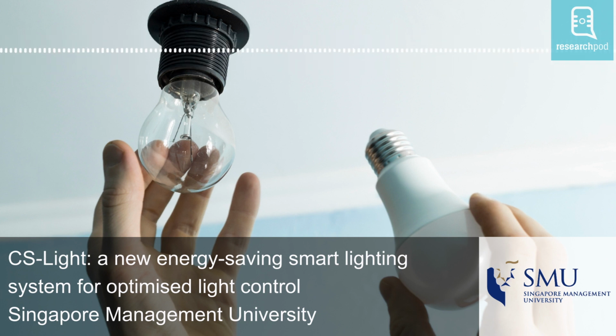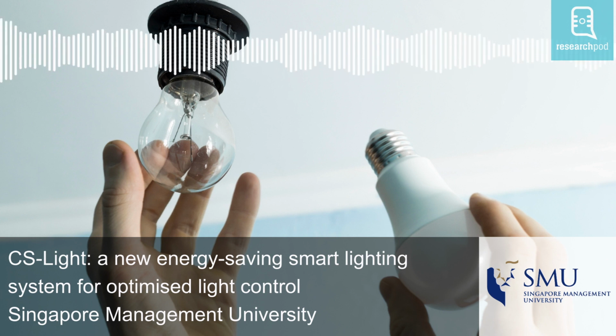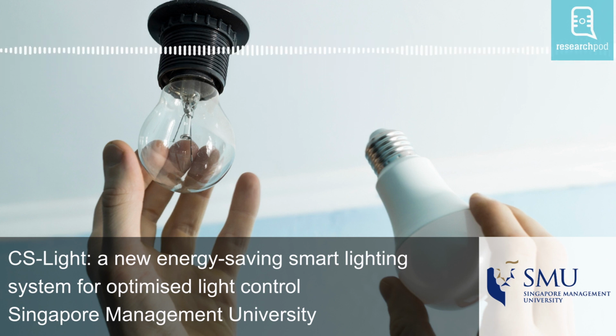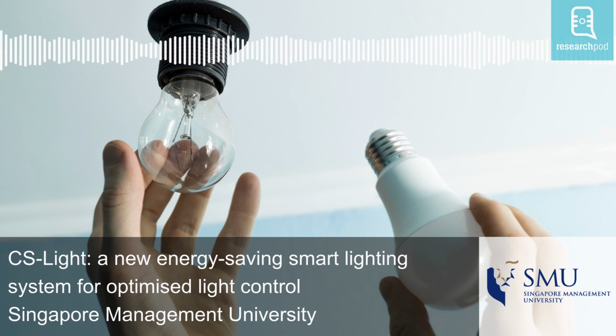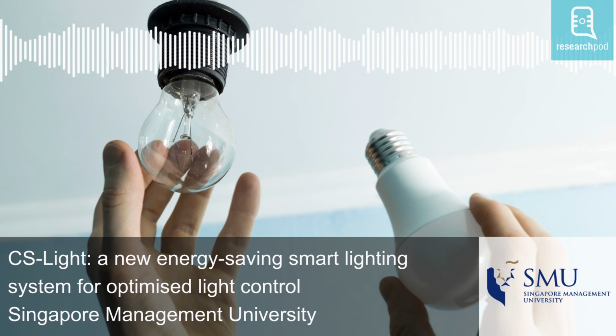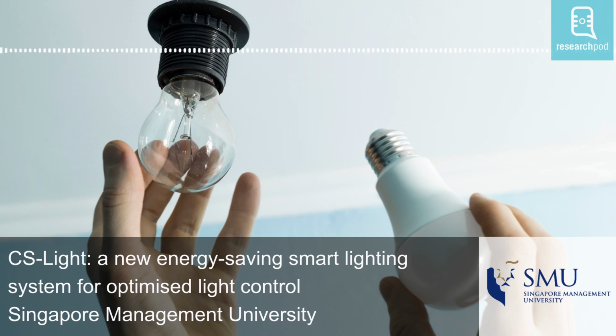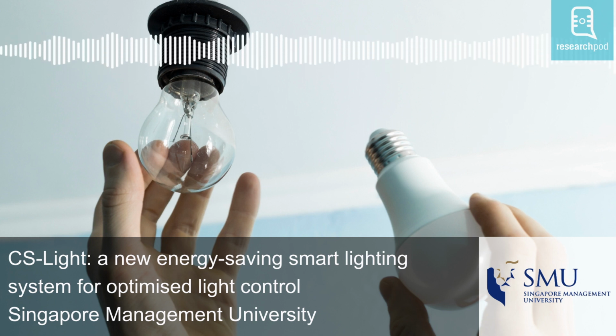Of course, any such LED adjustments were conducted gradually, no faster than once every 30 seconds, to avoid drastic changes in lighting that might distract human occupants. Within a collaborative workspace of around 100 meters square, the researchers demonstrated that the CS-Light system could achieve energy savings of 63.5% at low occupancy and savings of 37% at high occupancy. When workspaces were unoccupied, CS-Light can save as much as 79% in energy consumed by lighting.